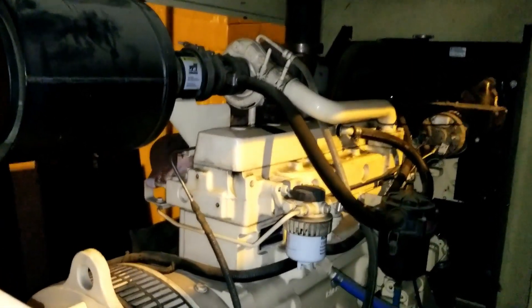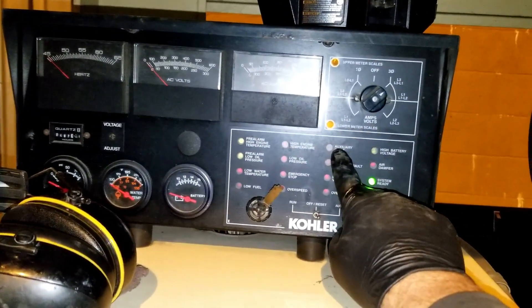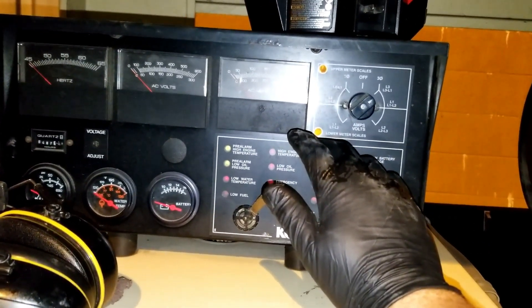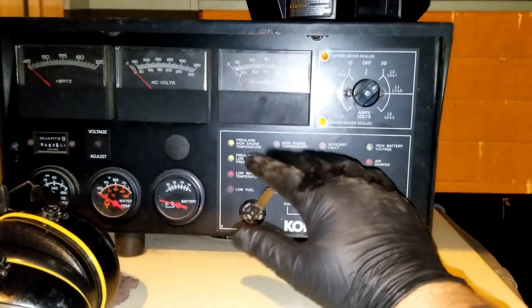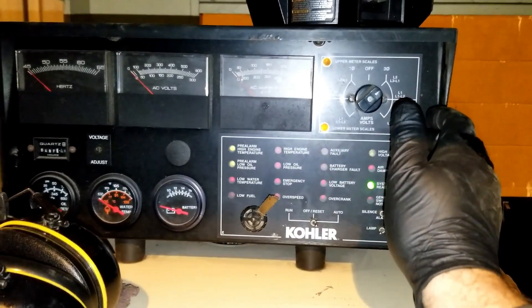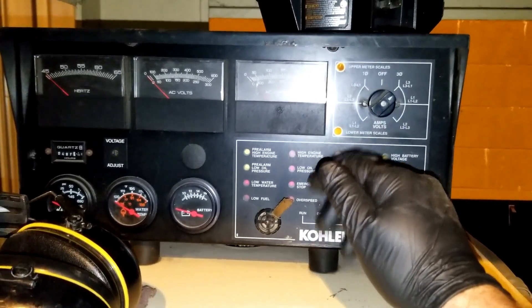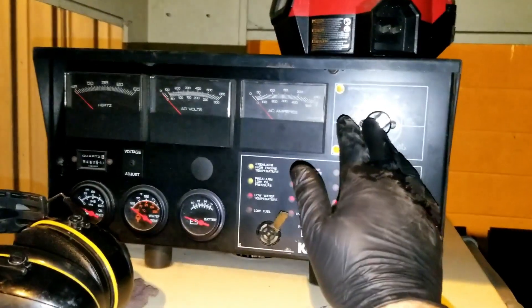Got the pump done, everything works perfect, but the unit's not producing voltage. Fire it up and it's giving me an auxiliary fault flashing light. Checked the frequency — it's producing about 61.8 hertz, which I find perfect. I like to run a little high because it's a mechanical governor — I want it to droop into speed once it hits full load, down to about 59.5 hertz. But we've got no voltage, so let me give you a quick explanation of what I did.